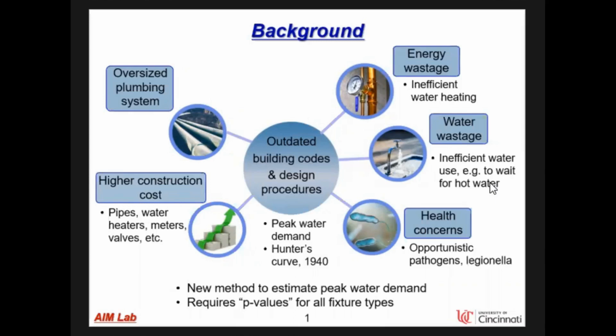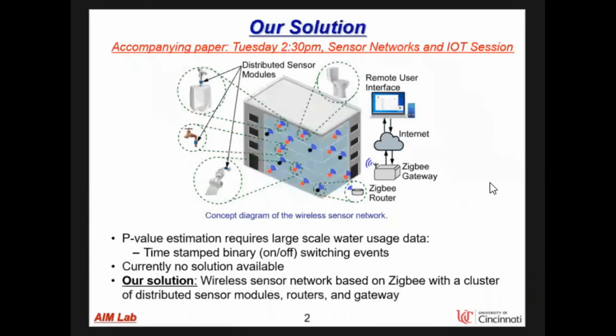Oversized plumbing systems can trigger potential problems such as higher construction cost, energy and water wastage due to inefficient water heating, and other health concerns like opportunistic pathogens like Legionella. A new method to provide a greatly improved estimate of peak water demand has been recently developed and adopted in the National Uniform Plumbing Code in the US. However, it requires a critical piece of missing information called the p-value, or probability of the fixture used during peak hours for all fixture types in a specific type of building.